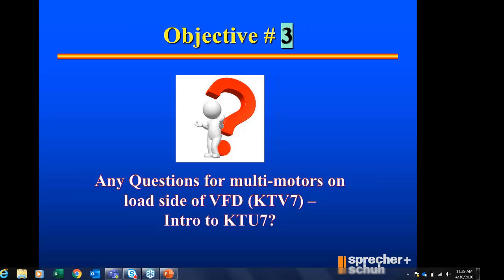And I guess the answer to that one would be, if your drive can handle the three motors and they all run at the same time and at the same speed, this is a way that you can actually have three motors controlled by one VFD, as opposed to providing three VFDs for that application. So it's a cost issue in that particular case.